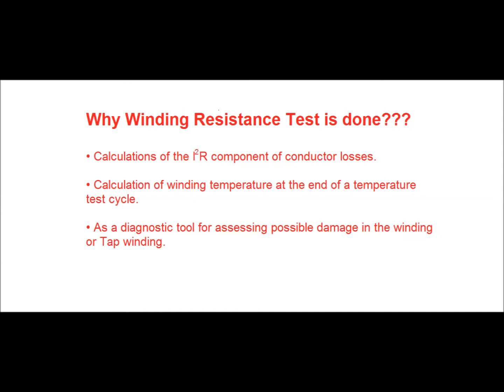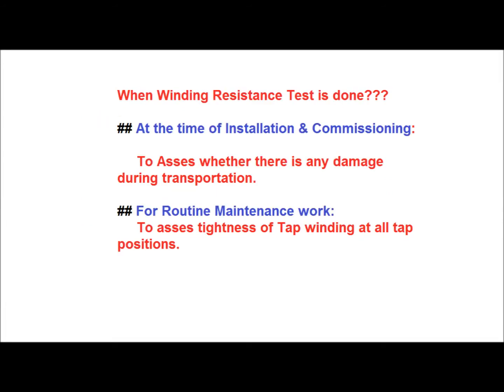measuring the resistance of the winding assures us that the connection of the winding with the tap winding is correct. Winding resistance measurement is done at the time of installation and commissioning of the transformer. Risk of damage is significant whenever a transformer is moved from one site to another. This damage can also occur during unloading and assembly. The damage will often involve a current carrying component such as the on-load tap changer. Damage to such a component may result in a change of DC resistance measured through it. Hence, it is recommended to measure the DC resistance on all taps before energizing the transformer.